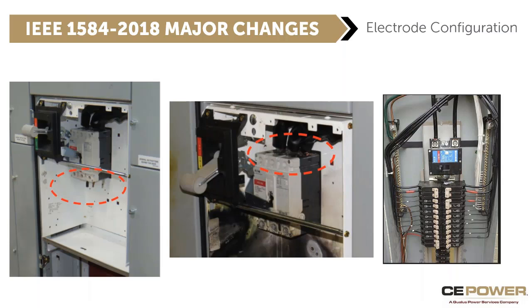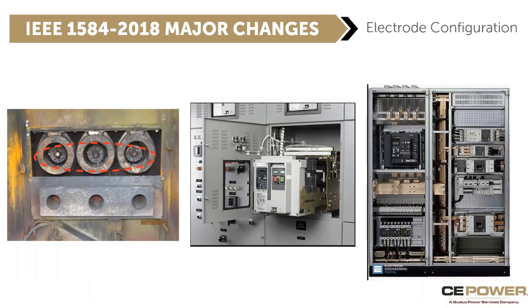Some of the software, if you're using the latest versions, has check boxes that you can check so that you consider both. And if you're working on the most up-to-date software, that's your best bet. If you can only look at one, it turns out that VCBB, 2 Bs, tends to be worse than VCB, but not always. So if you can only consider one, you should probably consider the one with the 2 Bs. And in MCCs, it's not realistic to consider HCB, which we'll look at now.